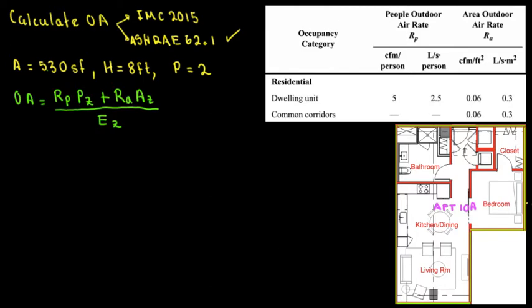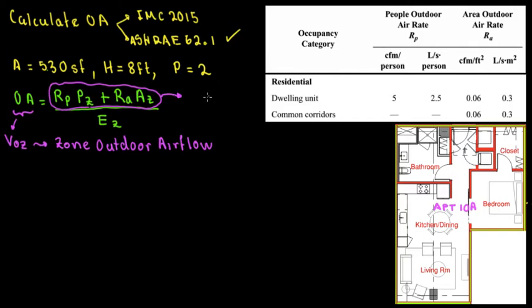But what is OA? Actually, OA is, in ASHRAE nomenclature, they call it as VOZ. VOZ, and VOZ is the Zone Outdoor Airflow. Let's just put that in here. This is the Zone Outdoor Airflow. And also, they call this equation, they call this, what they call in ASHRAE 62.1, based on the nomenclature, they call it VBZ, which is pretty much Breathing Zone Airflow.